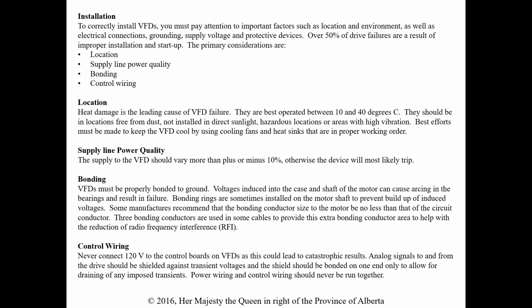The installation, again, we want to install them correctly. We pay attention to important factors such as environment, the electrical connections, grounding, supply voltages, and protective devices. Over 50% of drive failures are a result of improper installation and startup, so that's somewhat our responsibility. So we have to watch out for location, supply line power quality, bonding, and control wiring. And then location, heating again is an issue, probably the number one, that's what it says, the leading cause of VFD failure. They are best operated between 10 and 40 degrees Celsius. They should be in locations free from dust, not installed in direct sunlight or hazardous locations. Okay, again, just check through that stuff.